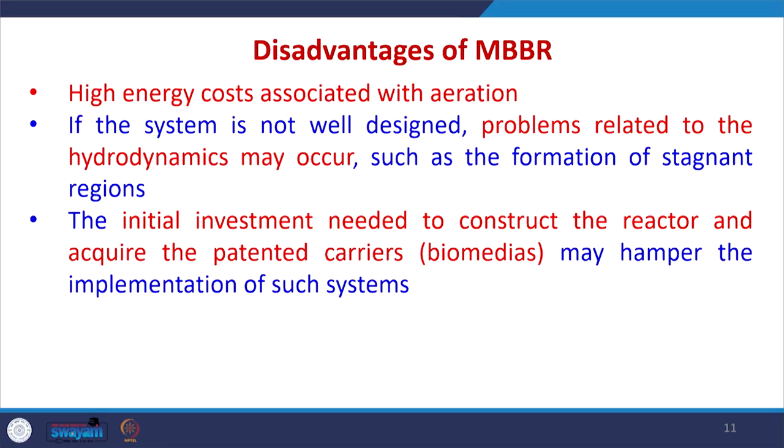So, we have advantages also as compared to fixed bed or trickling bed reactors. The system footprint can be reduced, and the treatment plant can be built much more compact, because we are using a higher concentration of microorganisms in the same reactor, and also the performance is increasing. The disadvantage of MBBR is the higher energy cost associated with the higher amount of aeration.